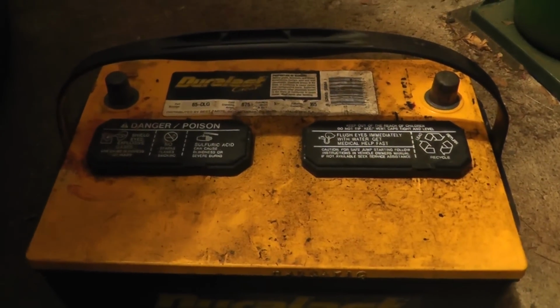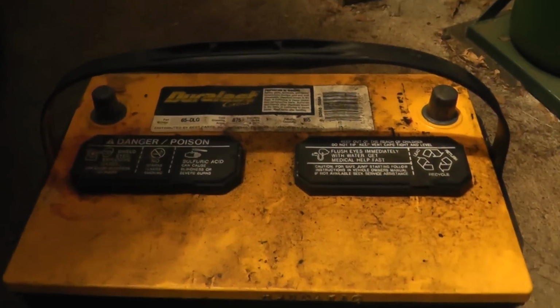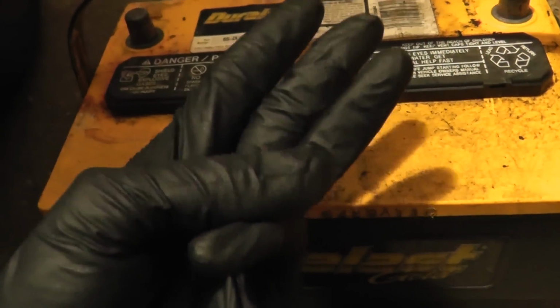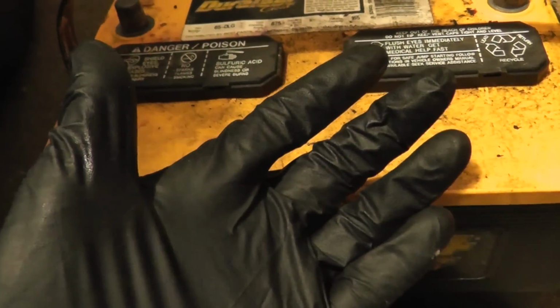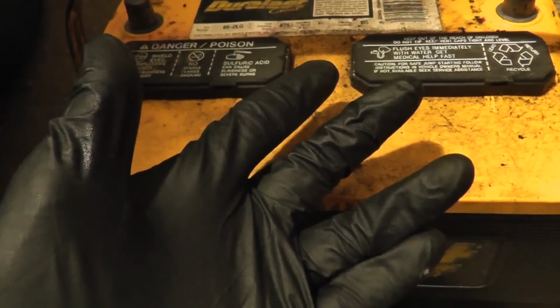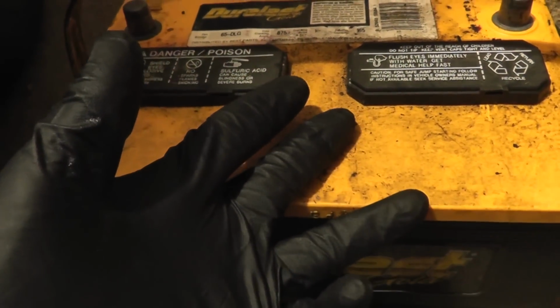Or you could use the date code, usually heat-stamped into the battery somewhere. On this battery it's stamped on the front. Look at the first two digits: a number and a letter. The number corresponds to the last digit of the year it was manufactured, so a 6 means 2006. The letter corresponds to the month, counting A, B, C, D, E, F, G, H, J, so J means month 9, September.